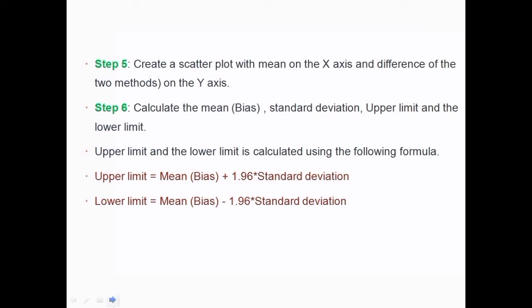Step six: draw three lines in the scatter plot. First is the mean, also known as the bias. Second is the upper limit. Third is the lower limit — these are known as the limits of agreement. The upper limit is calculated as mean plus 1.96 times the standard deviation. This means 95% of your data should lie between the upper and lower limits, and from that you can say whether the two methods are similar or not.